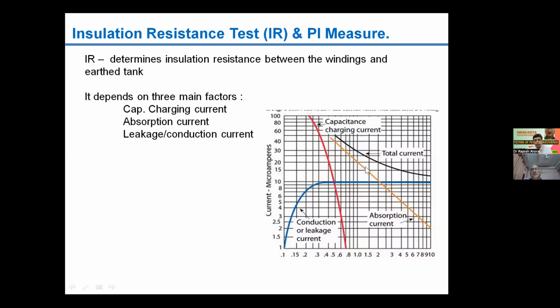Of the three currents, as you see in the graph, when we take the reading after 10 minutes, only conduction current will be there. The two currents, the capacitive charging current and the absorption current, will not be there. So that is the significance of why we take readings after 10 minutes and 1 minute, and the ratio is calculated, which gives fair information about the health of the insulation, which is indicated on the next slide.